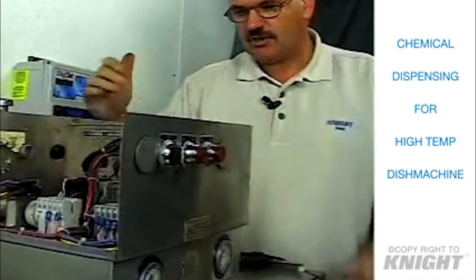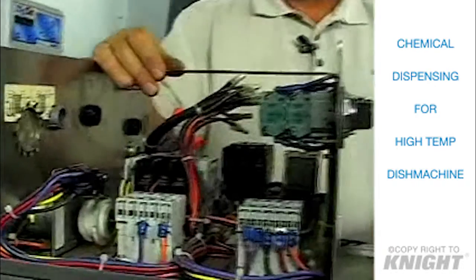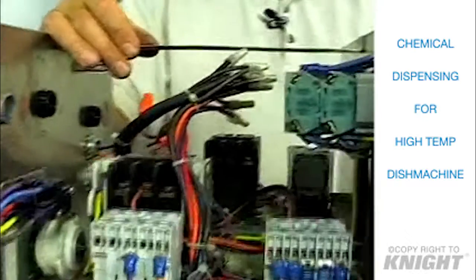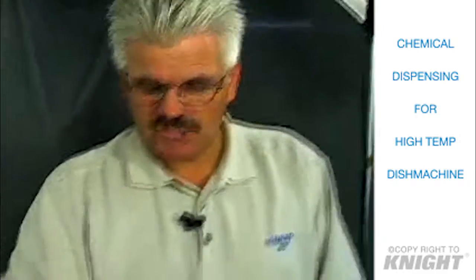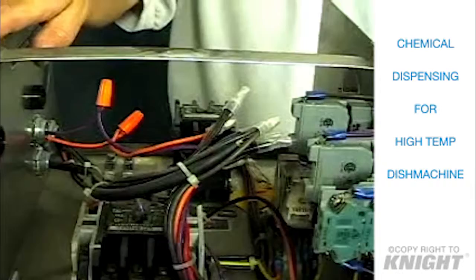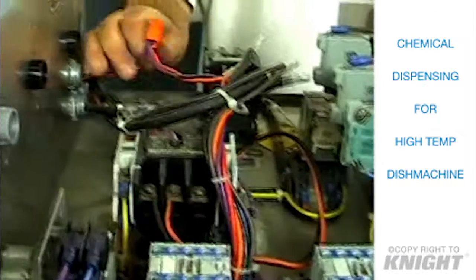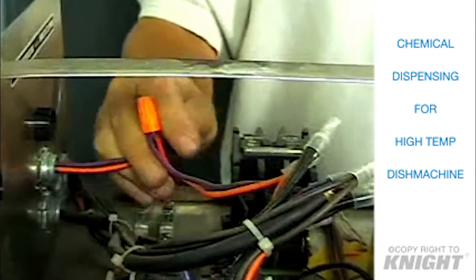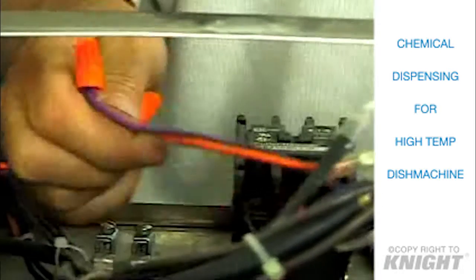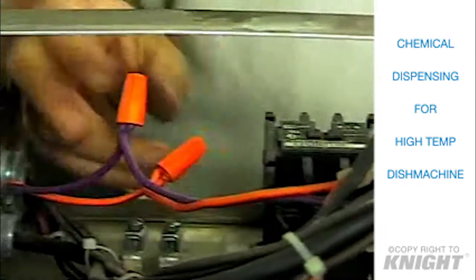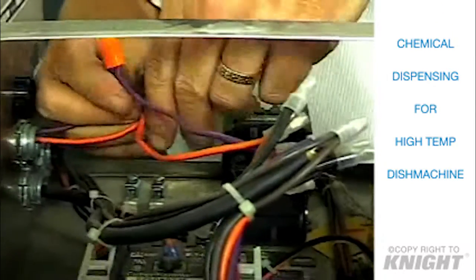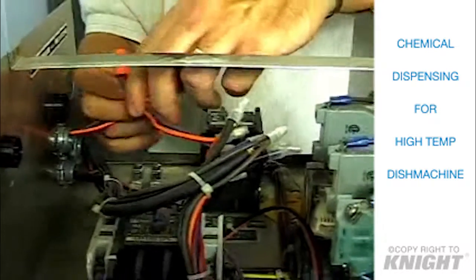If we come up inside to the control box, this machine has an automatic fill feature. So, and our connection for our rinse is right here, coming in from the rinse solenoid, so it's very easy to identify the orange and purple wire. So these two wires are going to go to our rinse signal.